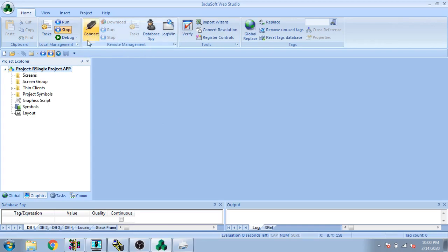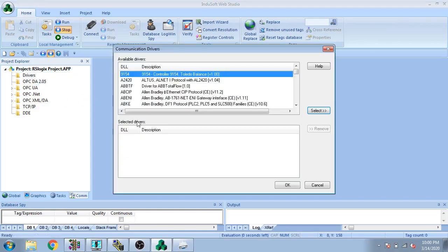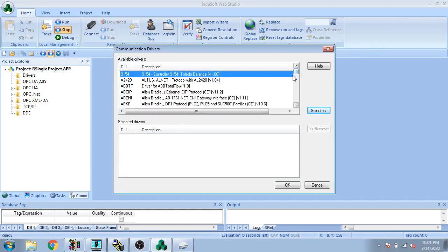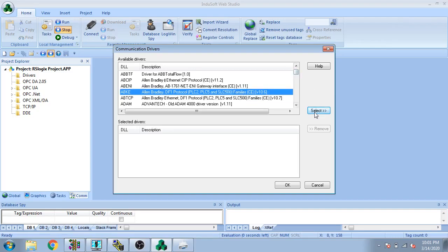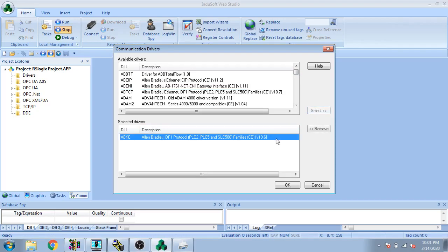Now I go to Communication, select Drivers, and Add and Remove Drivers. I need a driver so I select DF1 — you can see DF1 protocol for PLC2, PLC5 series. I select it; it is the DF1 protocol over serial, not Ethernet, so I select that and click OK.